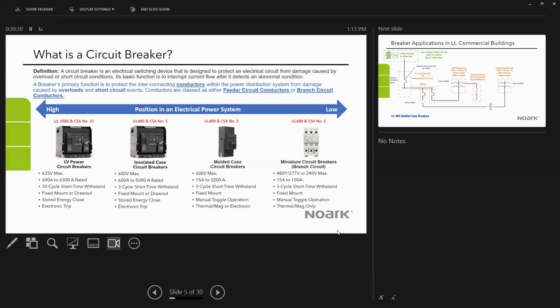So this slide is really intended to illustrate where the different breakers that are in the market are applied within those power systems. So on the very left-hand side, at the high end or the incoming part of a power system, this is where our low voltage power circuit breakers come in. They're typically rated up to 635 volts. That's the voltage class that's laid out in the standards. And typically they have an ampacity between 600 and 6,300 amps.